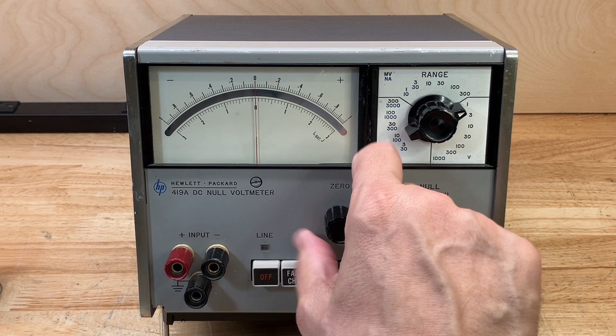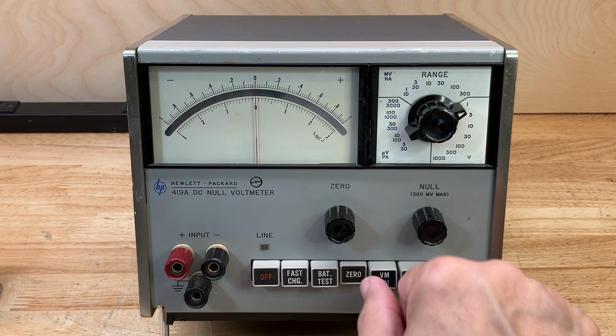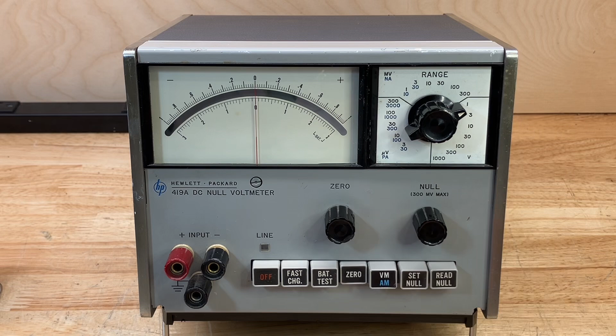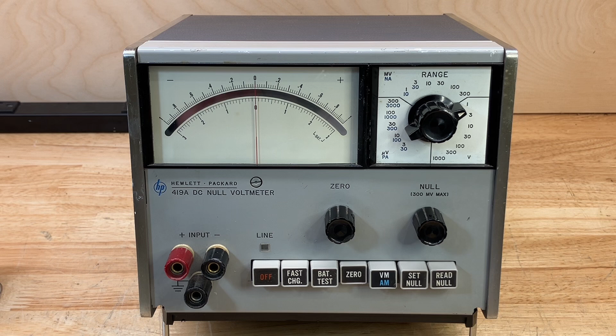When you select the zero function, an internal short is placed across the input, and you can use the zero potentiometer control to fine tune for a zero voltage, center-scale, zero indication reading. This is most important when you're down on the lowest ranges, because it's a very sensitive instrument and you want to be as close to zero as possible.